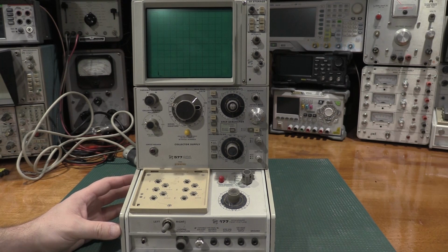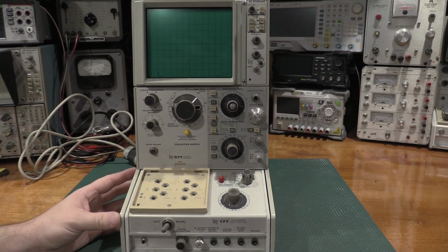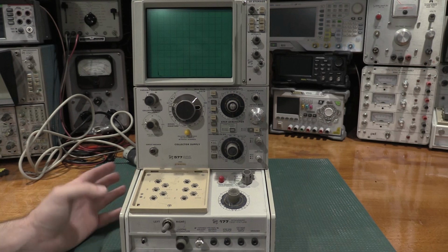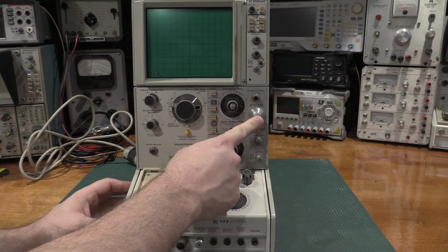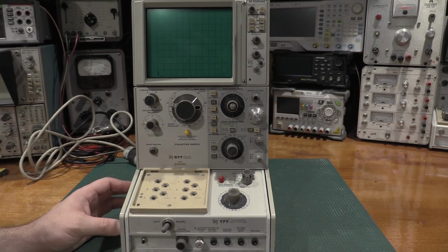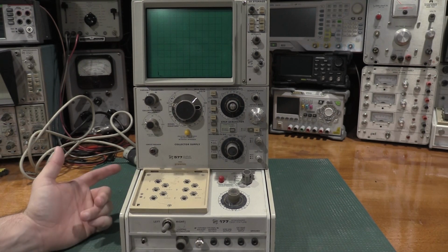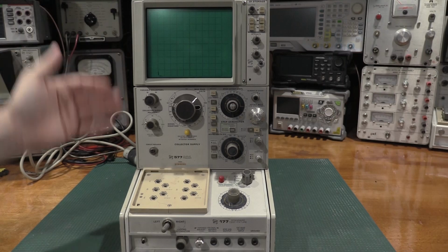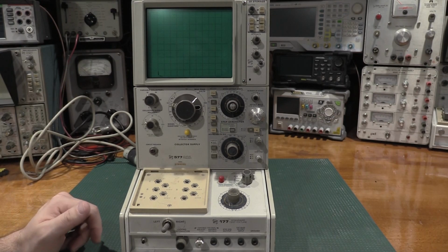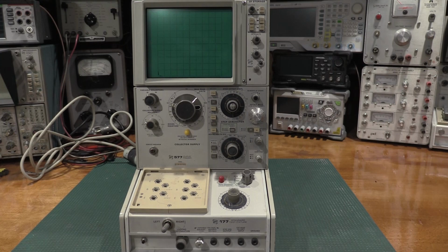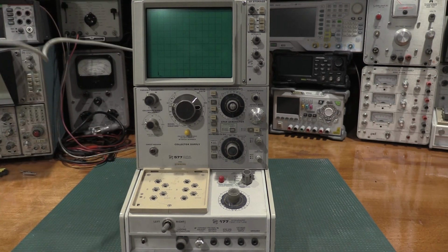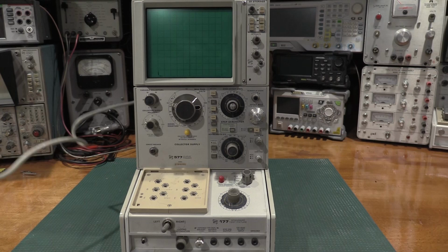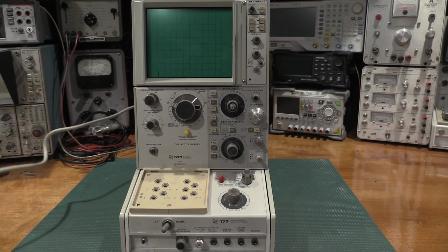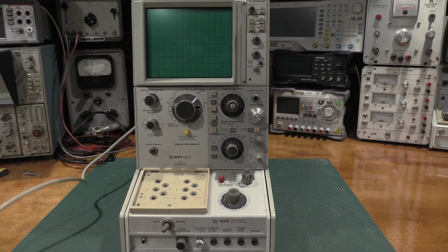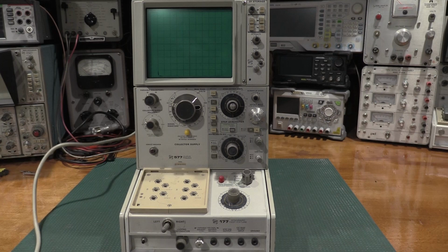A lot more to talk about on this one. This one had quite a bit of service life and some more options. So this control got fixed, no more plastic bezel holding that in, so not a concern on the 577. The tube on the 577, there are units that share that tube, so if you do get one with a bum tube, there are options to harvest them from other units, and those other units, in my opinion, are less useful on the bench than a curve tracer, so I did not mind.